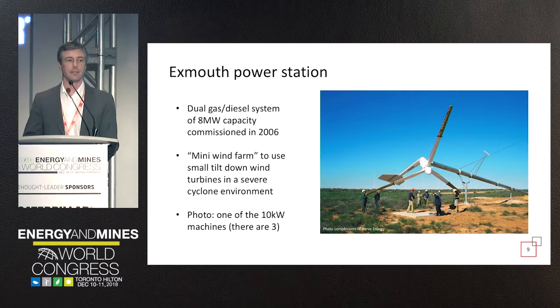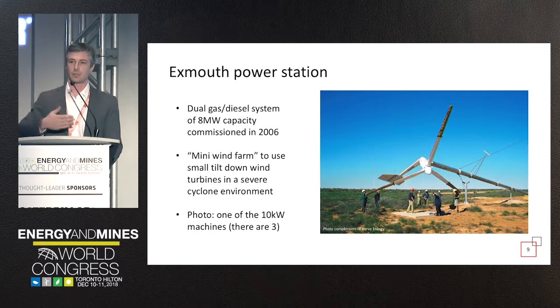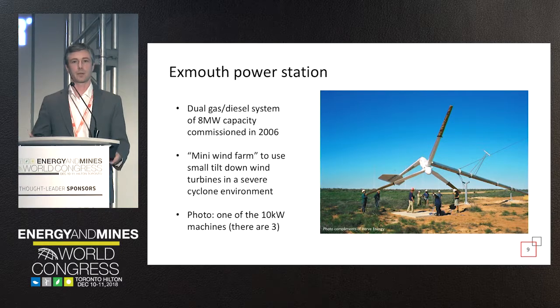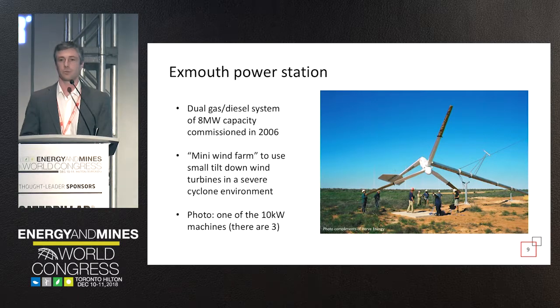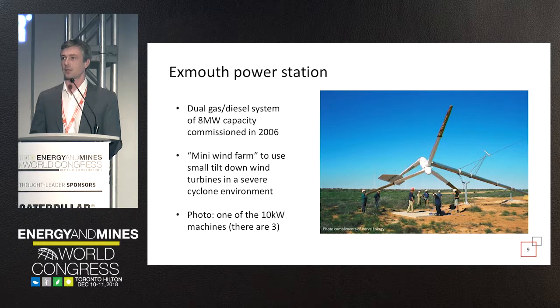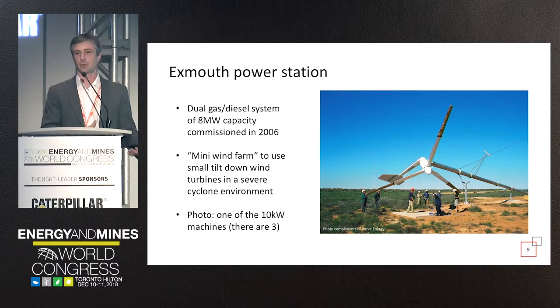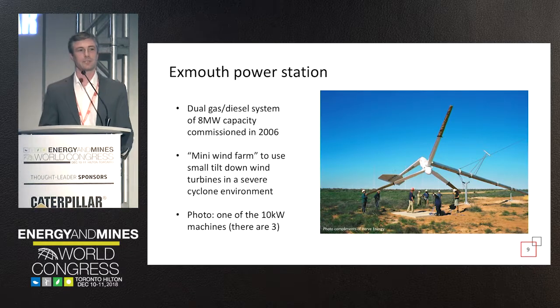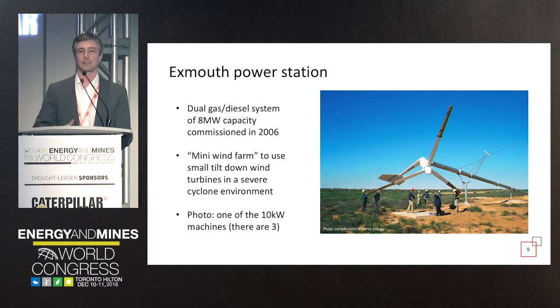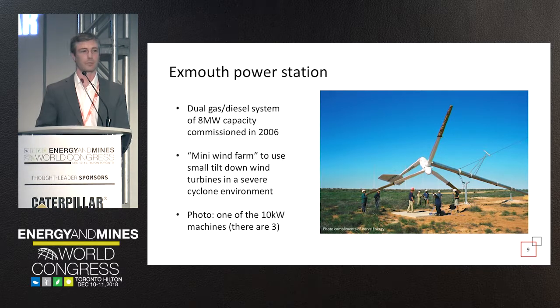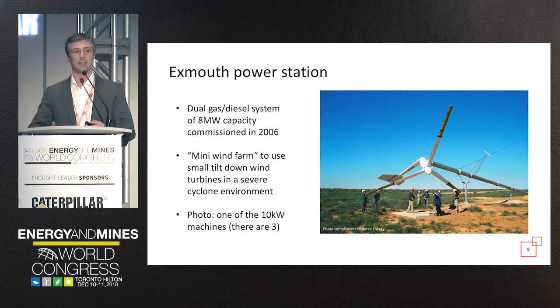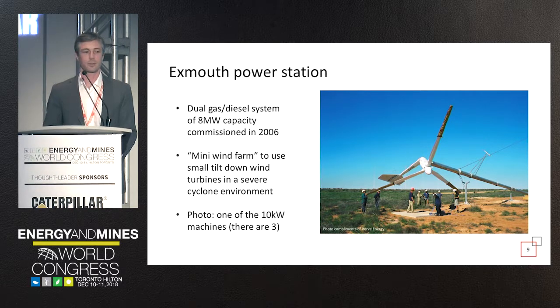To do that we've been innovative in several ways, including using tilt-down turbines in areas with a high risk of cyclones. If you're going to use renewable energy you expose yourself to different risks — you hedge against fuel price volatility but you're exposed to wind speed volatility. Using systems that can adapt as you get a weather forecast and know you have the opportunity to tilt your wind turbine down can make the difference in terms of risk and ultimate economic choice.